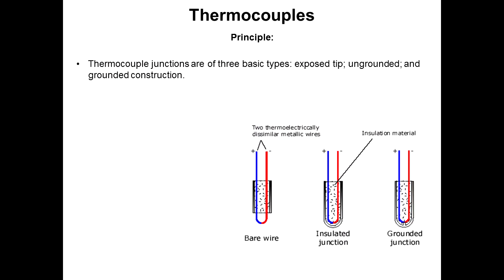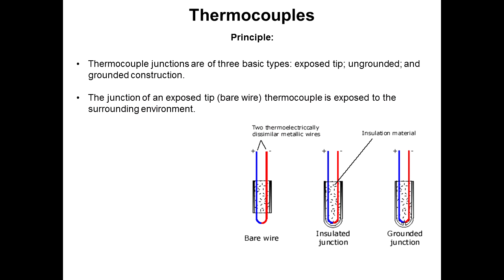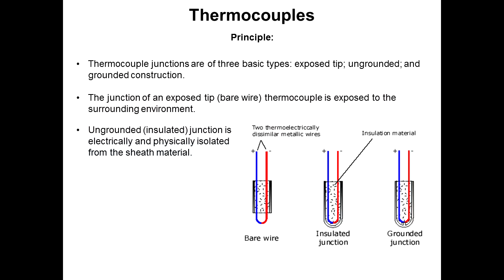Three basic types of thermocouples here. We have an exposed tip, and we have ungrounded and grounded construction. The junction of the exposed tip, which is a bare wire thermocouple, is exposed to the surrounding environment. That's fine for air, some powders, things like that, but it cannot be put into a conductive liquid. Ungrounded or insulated junctions are electrically and physically isolated from the sheath material. Those are good for control loops where you're not grounding your control loop out. They're a little bit slower in response, but they will work for control loops.